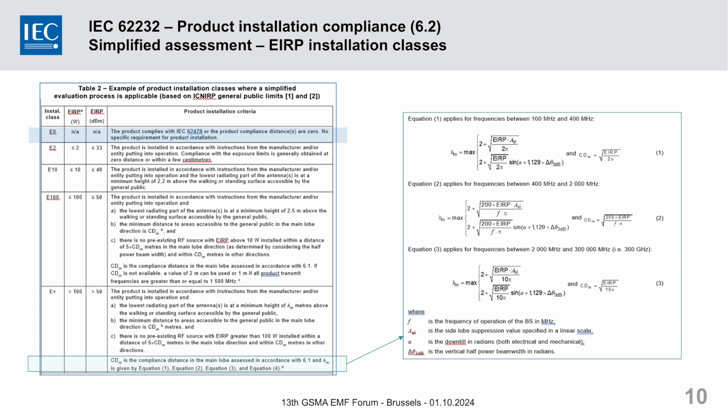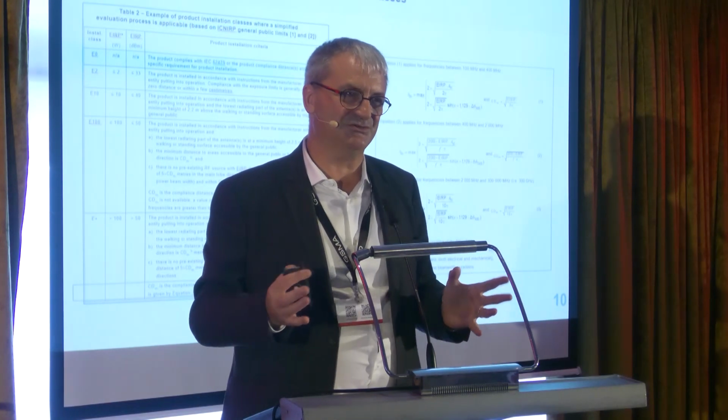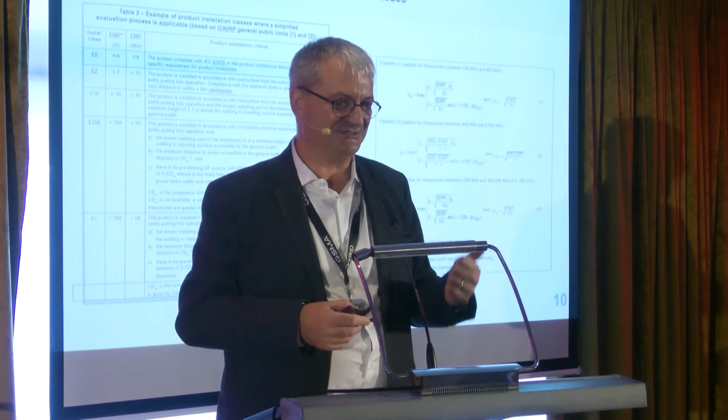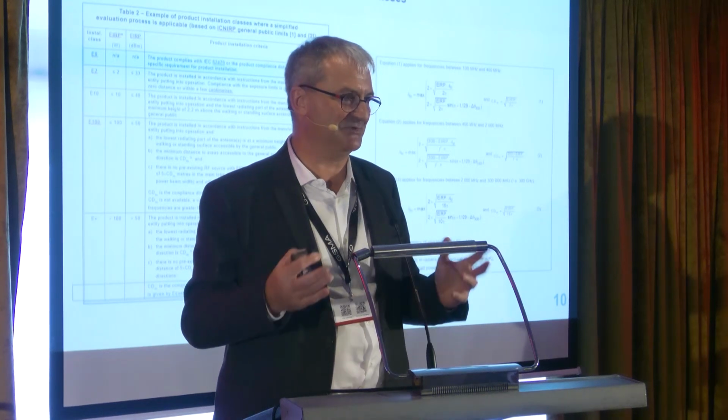And the last category is E+, where we can use the formulas provided on the right in order to calculate the minimum installation height without any need to do any other testing. Installation height and compliance distance in front and on this side. So this is a simplified approach which does not require any knowledge of EMF assessment, no big tool, etc.